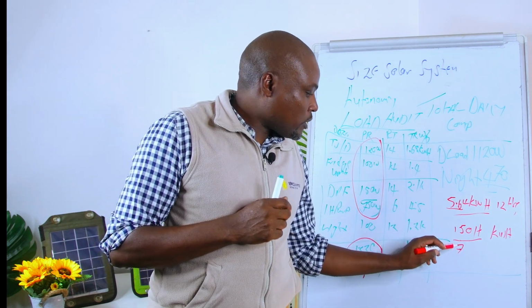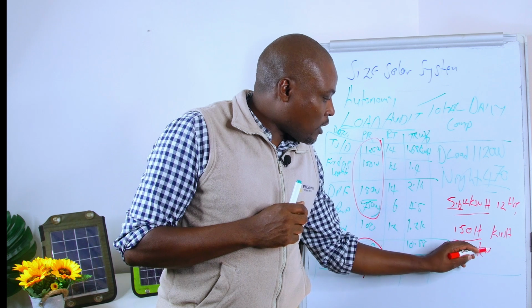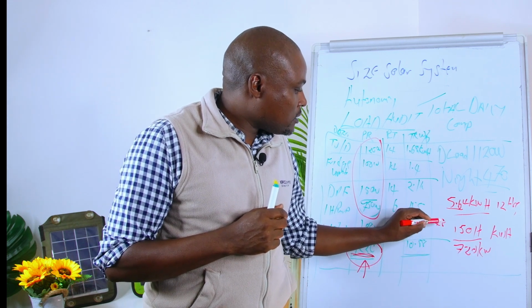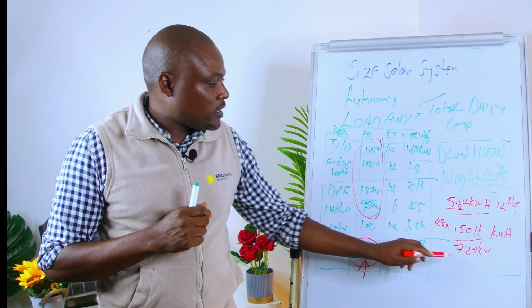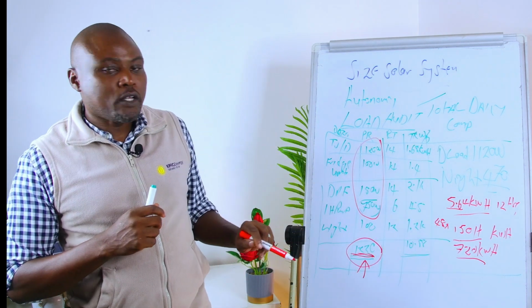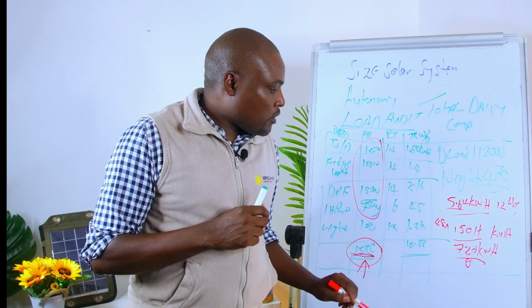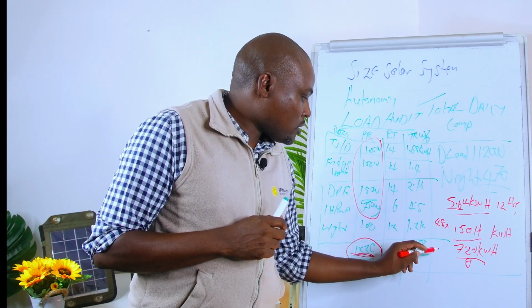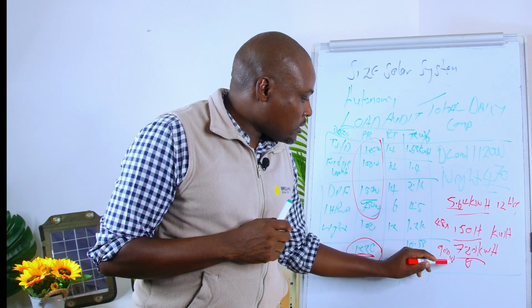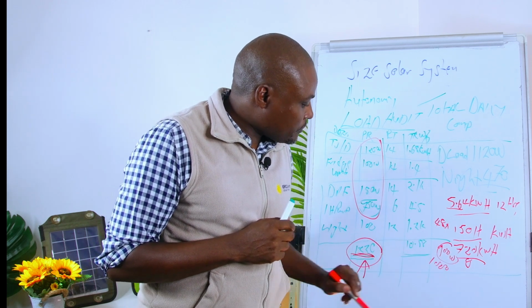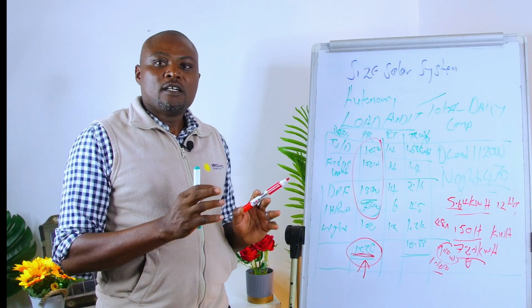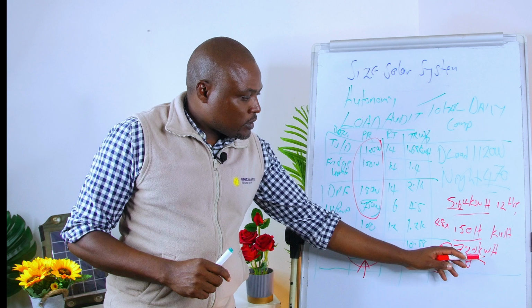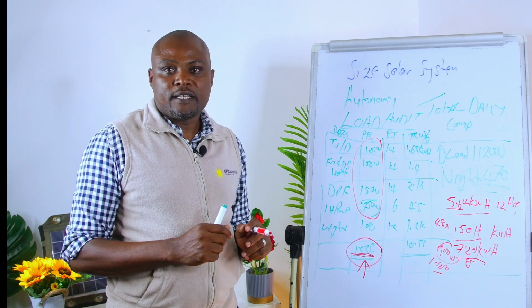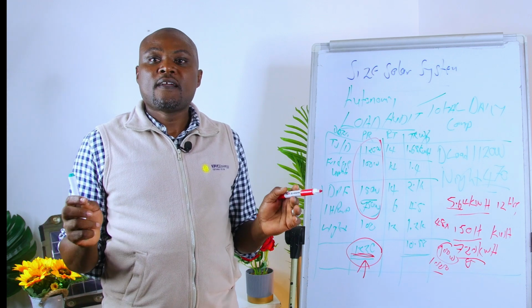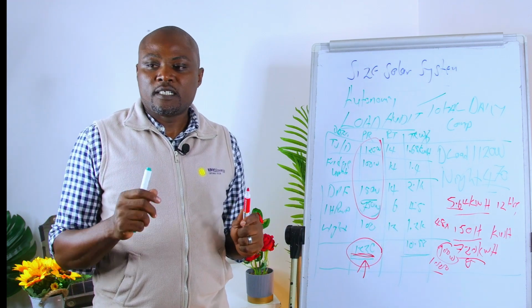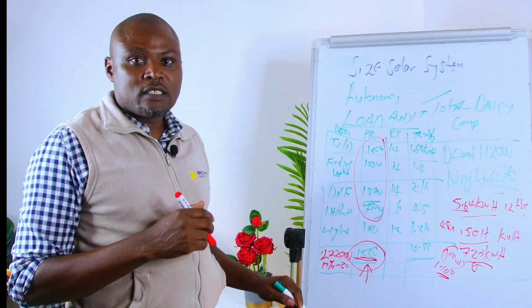So in this case, it's going to come to 7200 watt hours, because you calculate that by 48 by 150. Once you have the kilowatt hours, you divide this by 8 hours of day sunshine. I'm sure it's going to give you somewhere around 900 watts. So we just round this off to 1,000 watts, right? So which means every hour you need 1,000 watts for 8 hours in order to recharge that particular battery right there. So this is on a good sunlight day, and yeah, your battery will be fully charged 100%. We are saying we need 1,000 to charge up that 720 lithium.